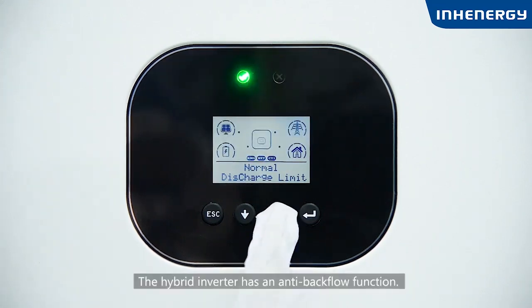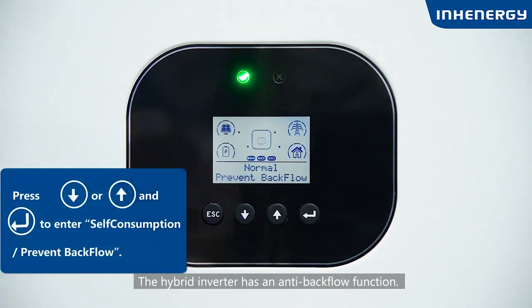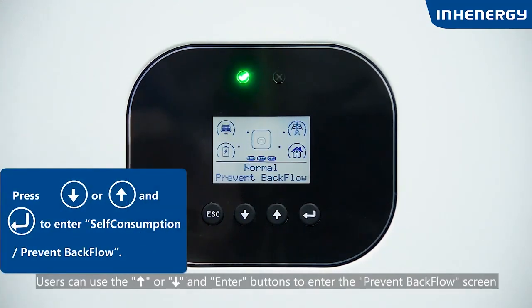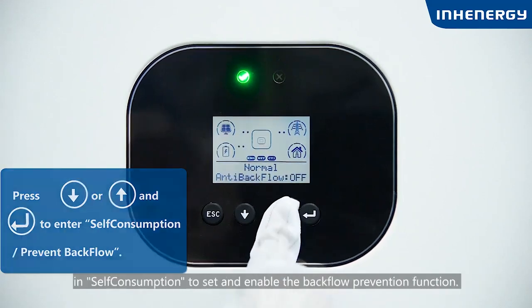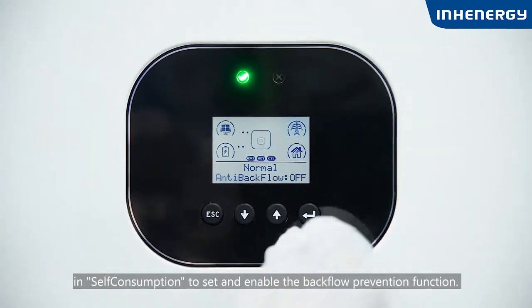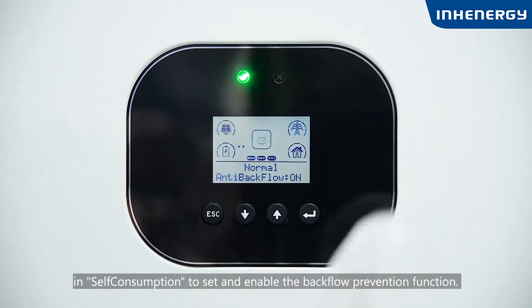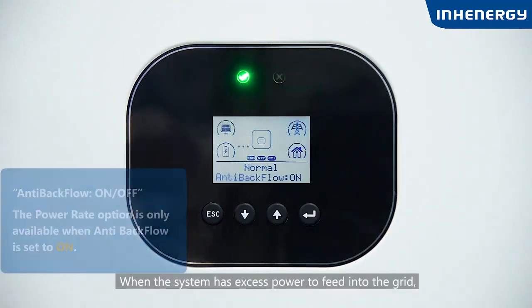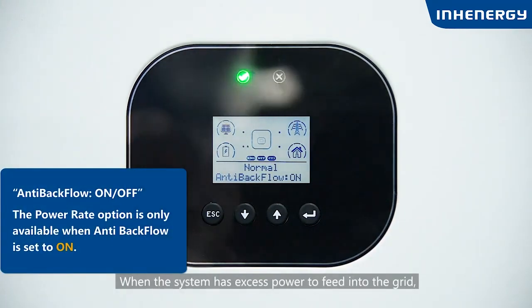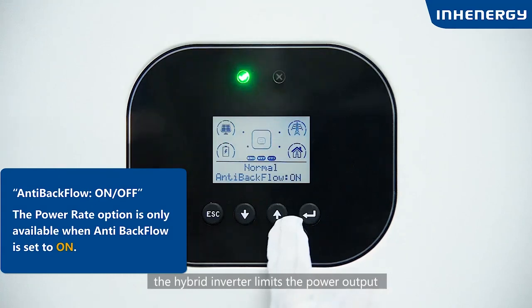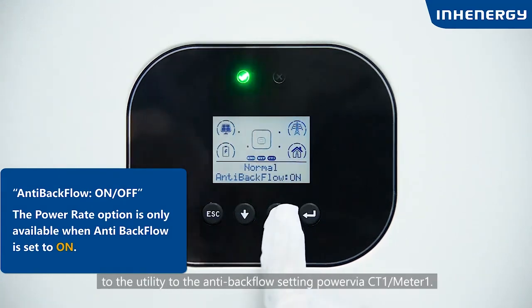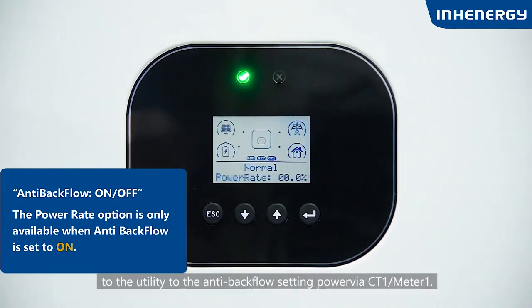The hybrid inverter has an anti-backflow function. Users can use the up or down and enter buttons to enter the prevent backflow screen in self-consumption to set and enable the backflow prevention function. When the system has excess power to feed into the grid, the hybrid inverter limits the power output to the utility to the anti-backflow setting power with CT1 or Meter1.